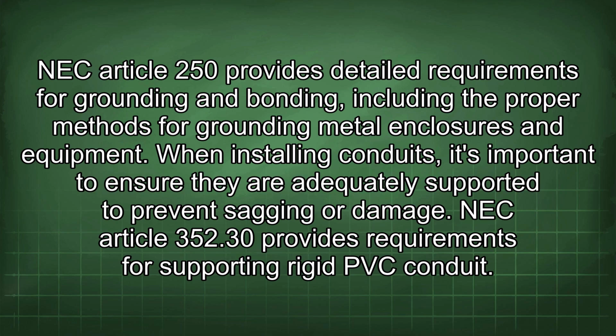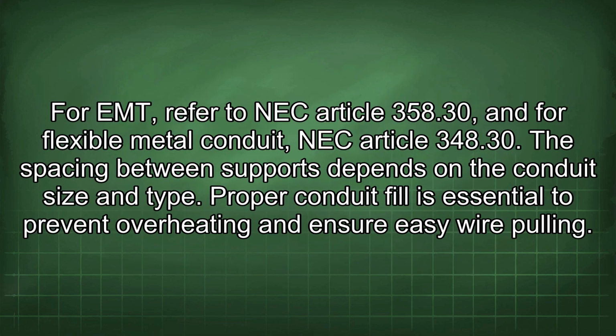When installing conduits, it's important to ensure they are adequately supported to prevent sagging or damage. NEC Article 352.30 provides requirements for supporting rigid PVC conduit. For EMT, refer to NEC Article 358.30, and for flexible metal conduit, NEC Article 348.30. The spacing between supports depends on the conduit size and type.